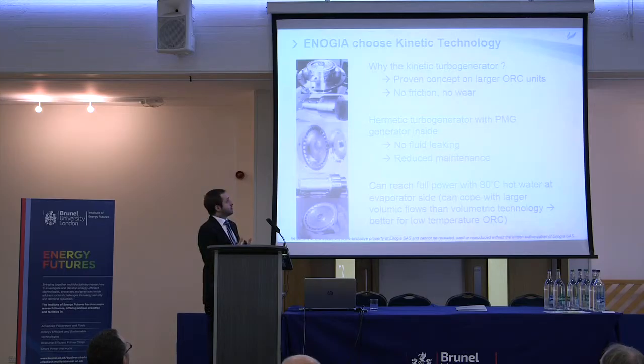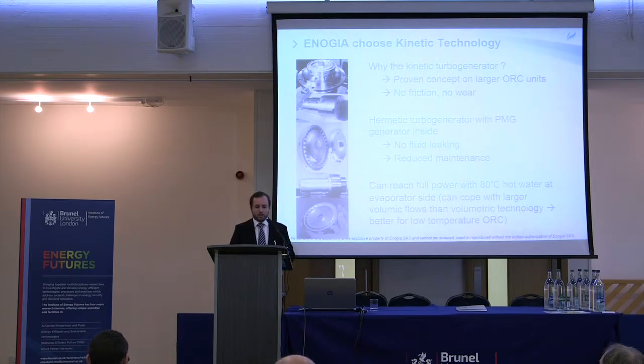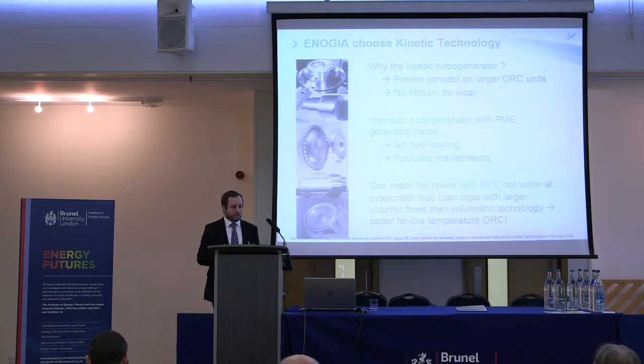So Enogia chose to develop an expander based on kinetic turbine technology, because it's a proven concept at larger ORC scale and has no friction, no wear. We also chose to include the permanent magnet motor inside a hermetic housing within the turbine generator, because this lets us get rid of the mechanical shaft seal.